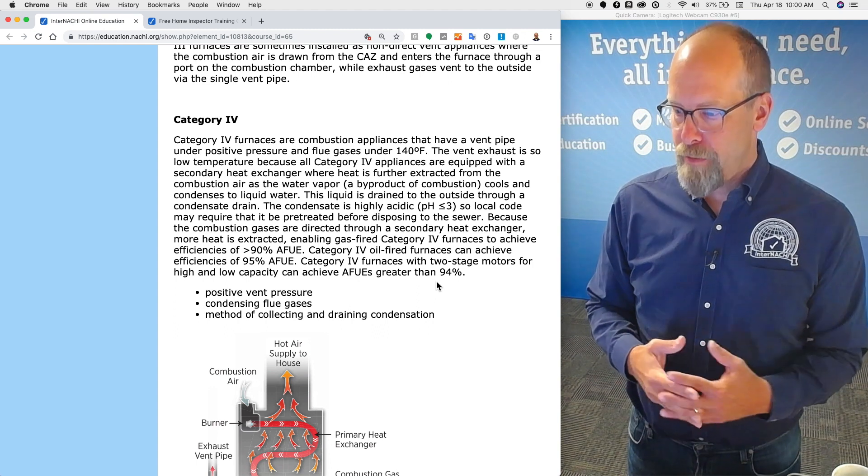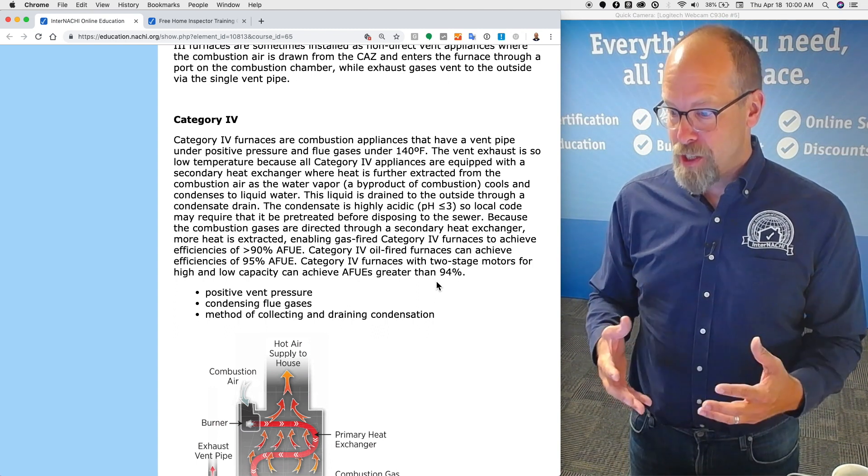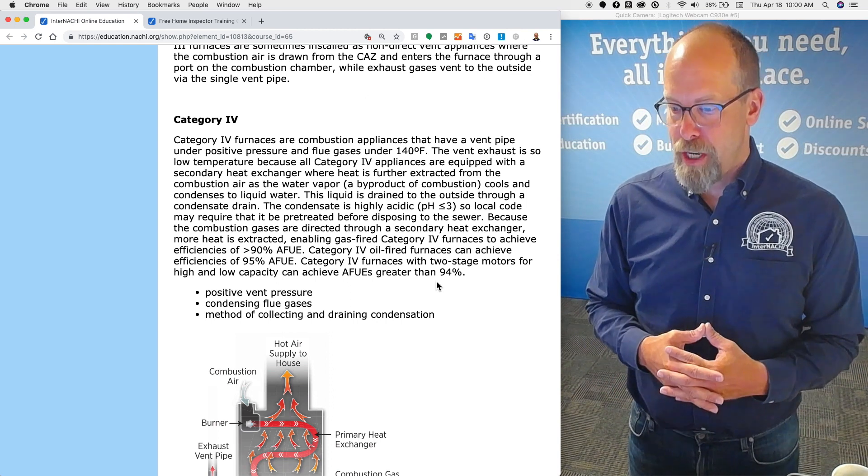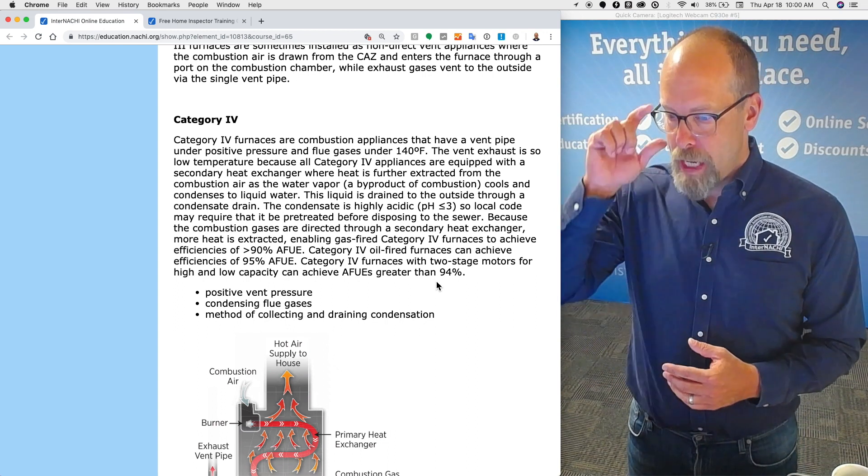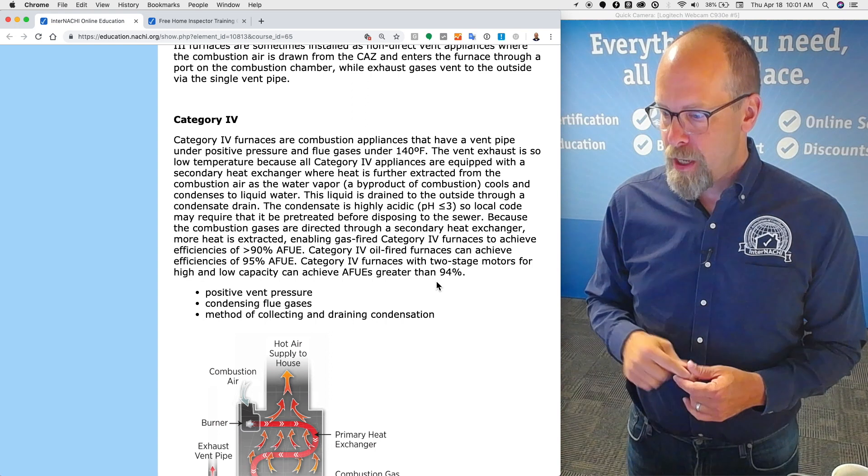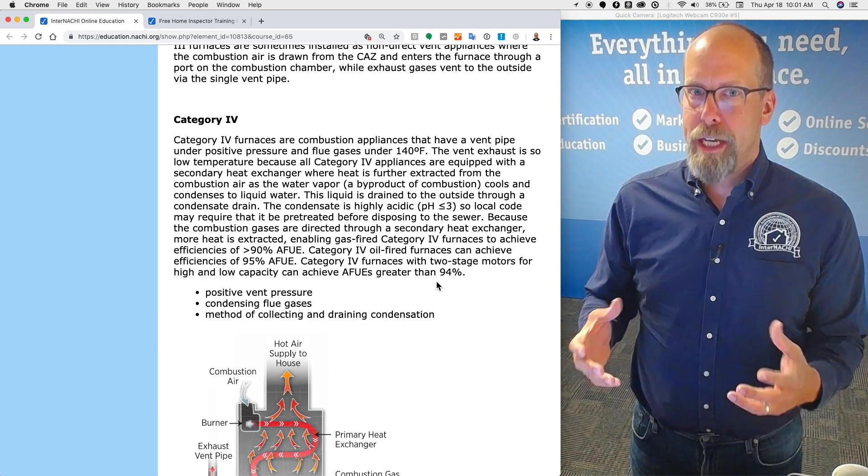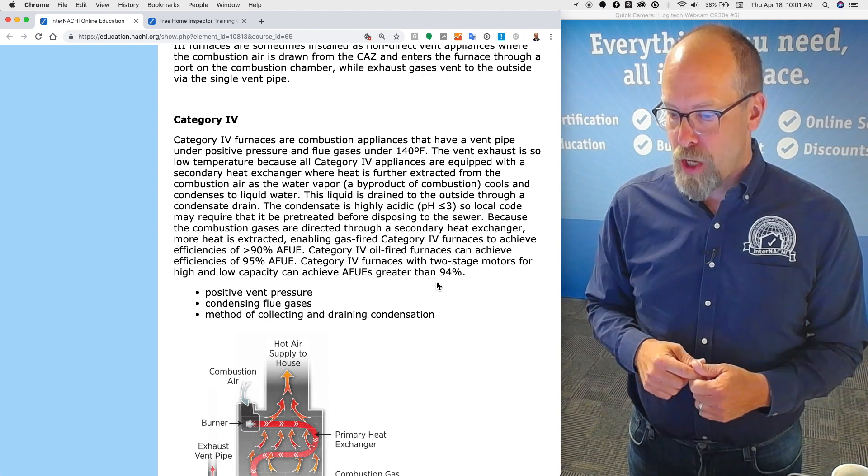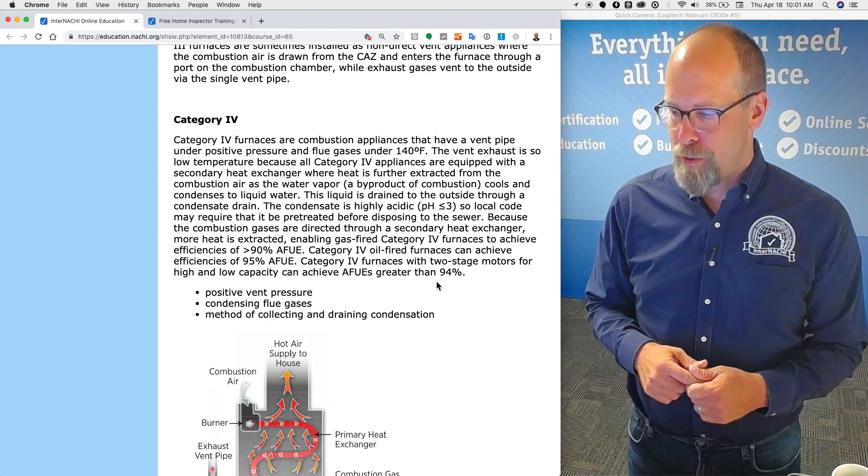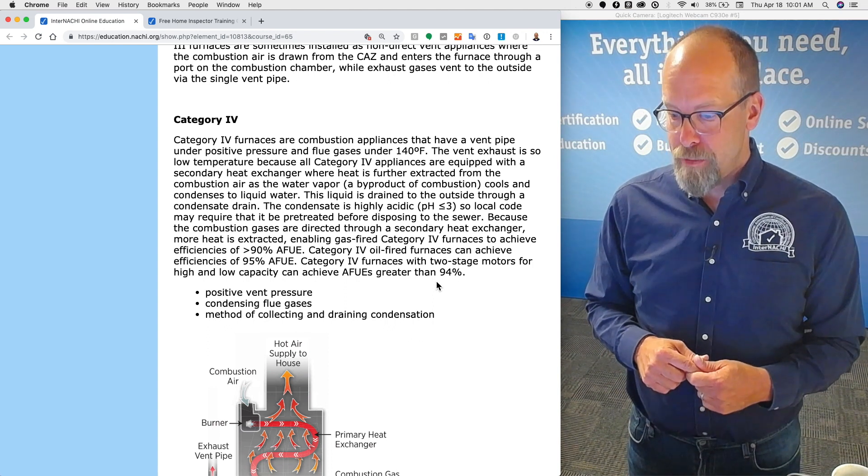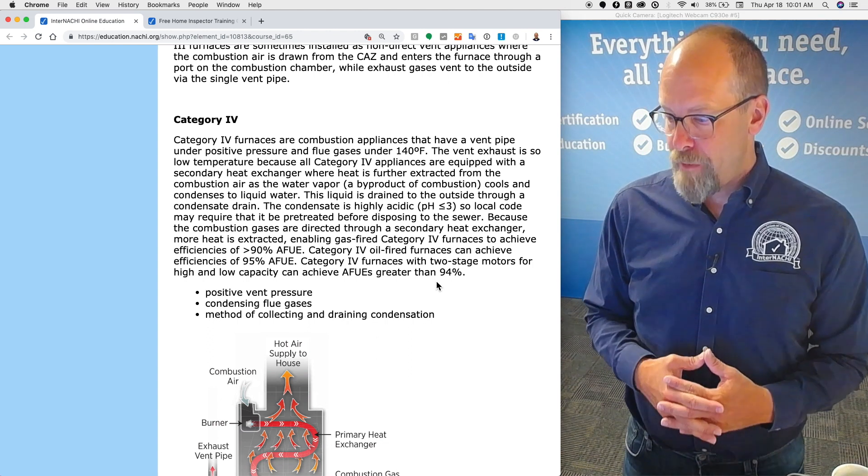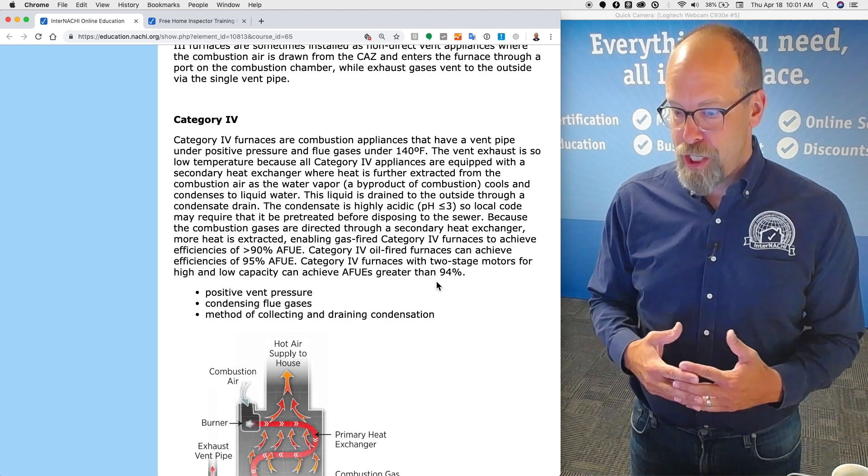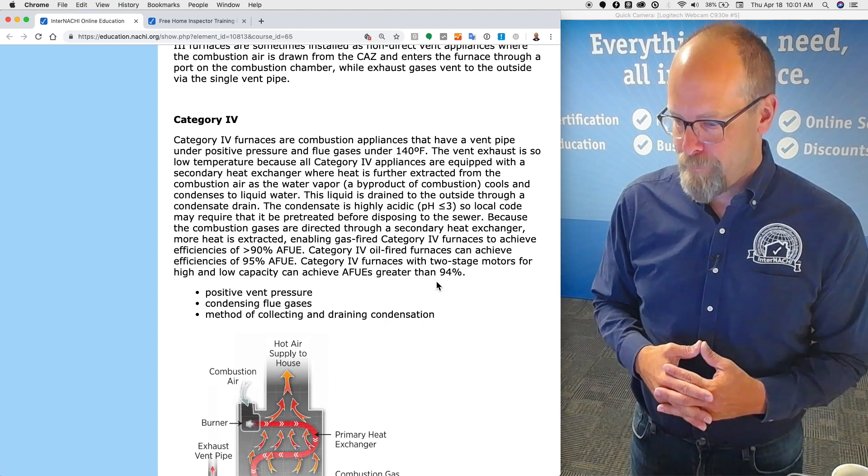That heat exchanger further extracts from the combustion air as the water vapor, a byproduct of combustion, cools and condenses into liquid water. This liquid is drained to the outside through a condensate drain, usually a collection pump. The condensate is highly acidic, so local code may require it to be pre-treated before disposing into the sewer. Because the combustion gases are directed through a secondary heat exchanger, more heat is extracted, enabling a gas-fired category four furnace to achieve efficiencies greater than 90 percent. Only 10 percent of energy is wasted.